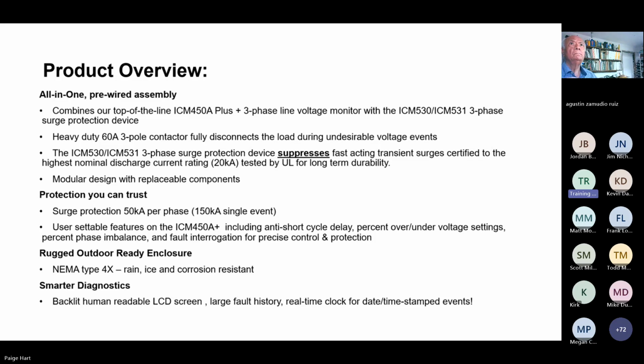And that would give you both voltage monitoring and surge suppression, which it would, but then you could only break a control voltage with the 450A plus. You wouldn't be breaking that service voltage. And also it would require, if somebody did want to break the service voltage, a contractor to install their own little box and kind of put all these pieces together. We do it for you all in one.